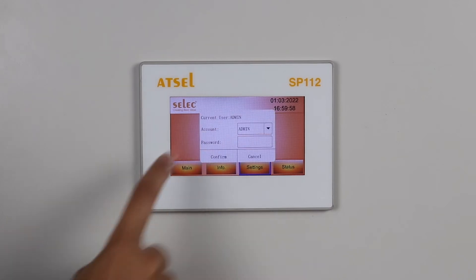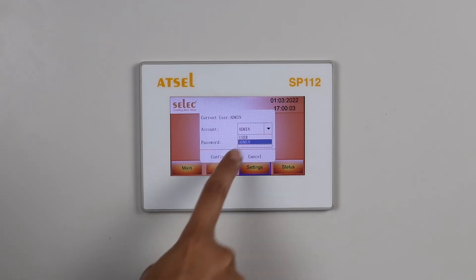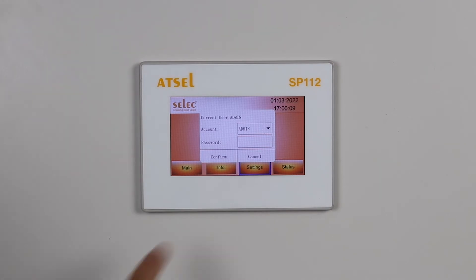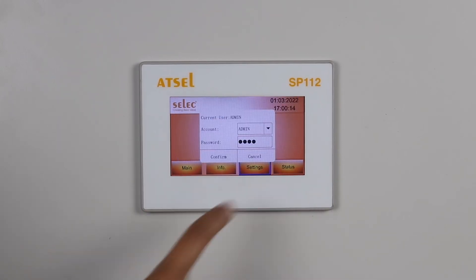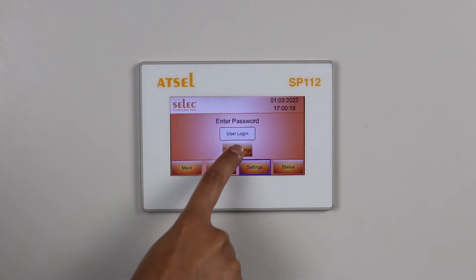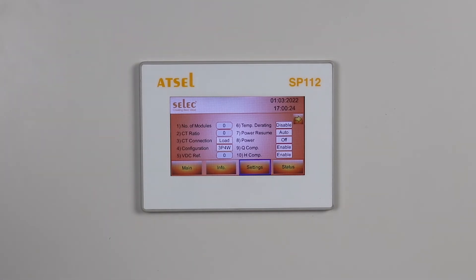In settings, you have to first log in. If you log in as admin, you get access to all the parameters. In user mode, you do not get access to all the parameters. Please enter the password to log in. In system variables, there are various parameters like: number of modules — that is, how many such modules are connected — CT ratio, CT connection, and where the CT is connected (grid side or load side), which you can set from here.